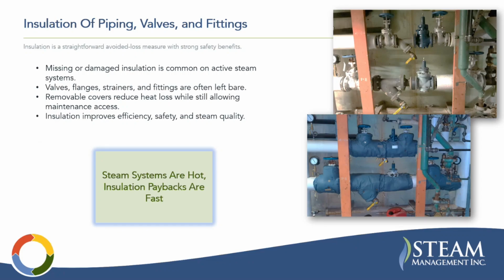Insulation of piping, valves, and fittings. Missing or damaged insulation is common on active steam systems. Valves, flanges, strainers, and fittings are often left bare, as you can see in the photo here. The top photo is before insulation, bottom is after insulation of the same section, although the coloring is a little bit different. You can see there's going to be a lot of energy conserved here. This isn't damaged insulation. They just left this off, right?